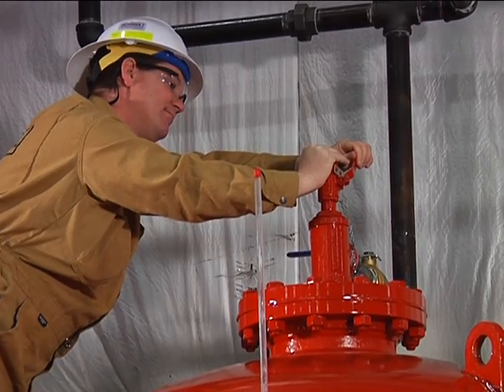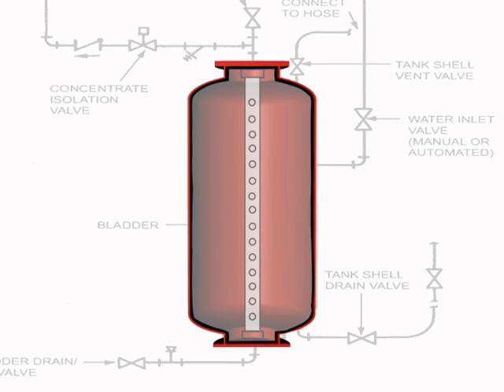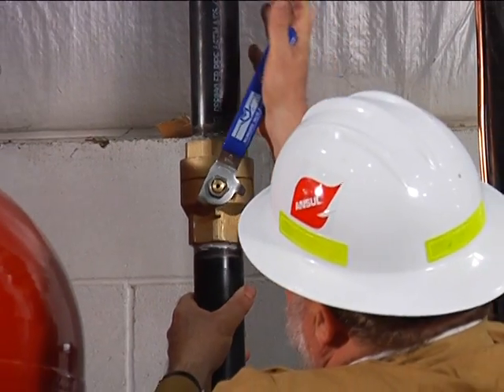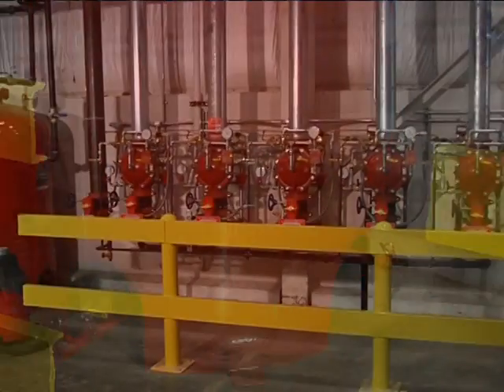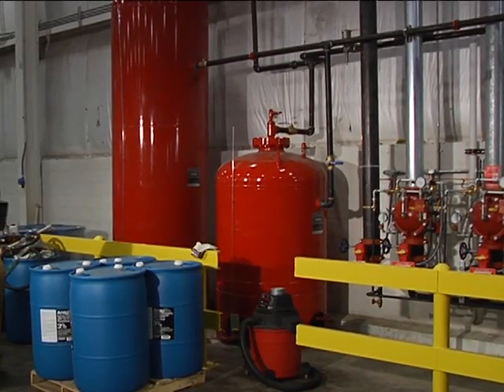When frothy foam appears, quickly close the bladder vent valve. Now all the air has been vented from both around the outside of the bladder and internal to the bladder. At this point the water inlet valve can be turned to the fully open position. Be sure to rinse any foam concentrate off painted surfaces. You're now almost through with the initial fill procedures for ANSUL's bladder tank.